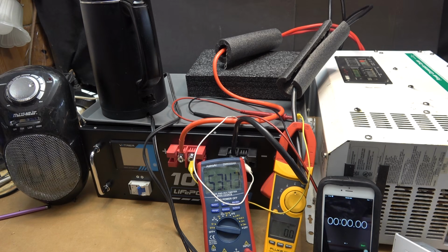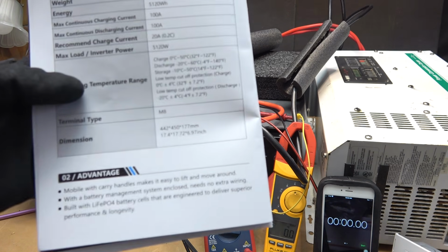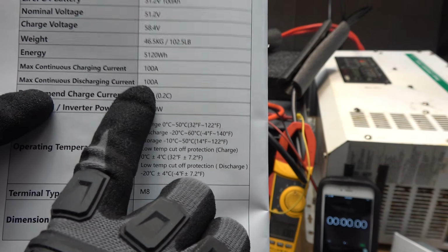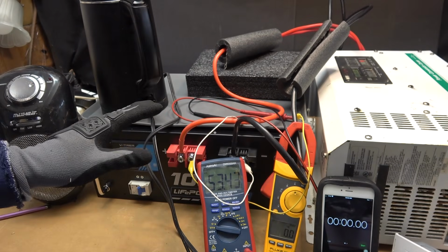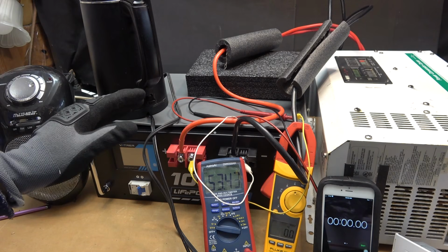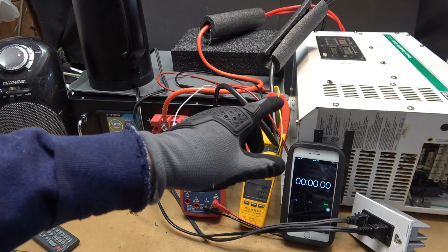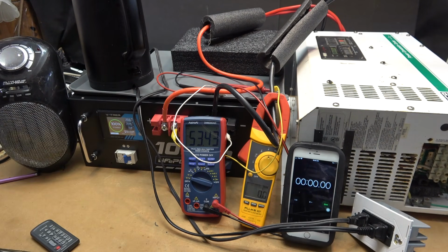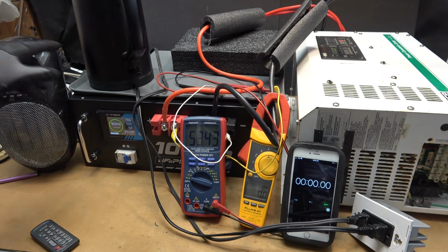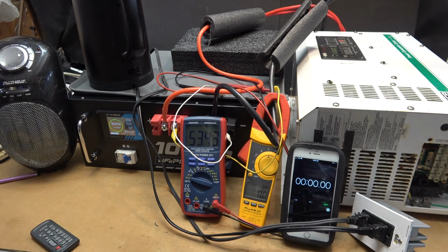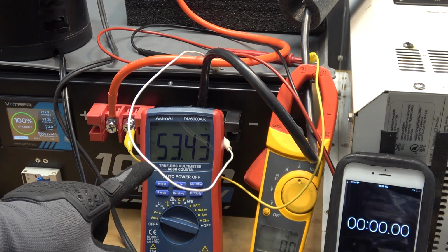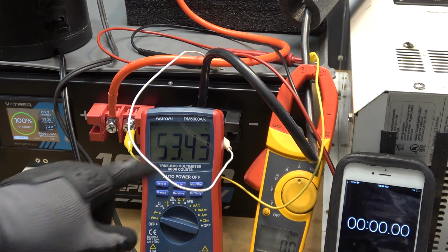It's time for a load test. This battery is rated at 100 amp maximum continuous discharge, and I want to see how it runs when it's under 100 amps. I've got a 4000 watt inverter connected to the battery. I've got a 1500 watt electric kettle and a 1500 watt heater connected to the inverter. The battery voltage right now is 53.43 volts.